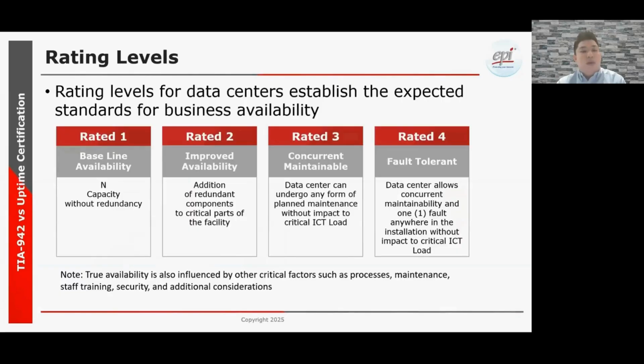Let's talk about the requirements of each rating. Rated 1 is baseline availability - capacity without redundancy. Rated 2 adds redundant components to critical parts of the facility. TIA recognizes that different data centers have different criteria for business availability, so we have differences from 1 through 4. Rated 3, the famous one, is concurrently maintainable.